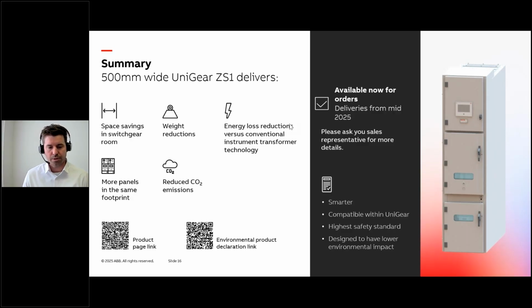So either to have it with instrument transformers, or with low power instrument transformers. The reduction of CO2 comes hand in hand thanks to the low power instrument transformer version, using current sensors and voltage sensors instead of traditional instrument transformers, which is much more energy efficient. And thanks to the narrow width, more panels can fit into the switchgear room.